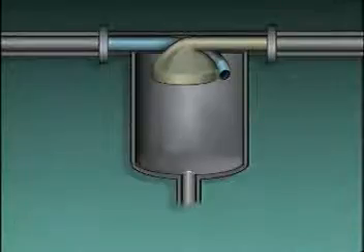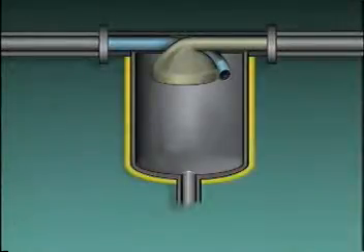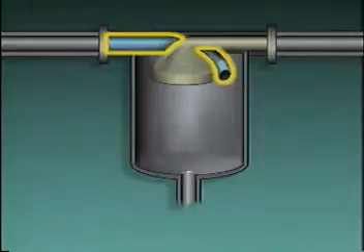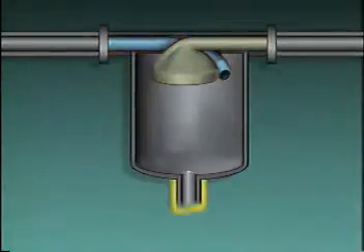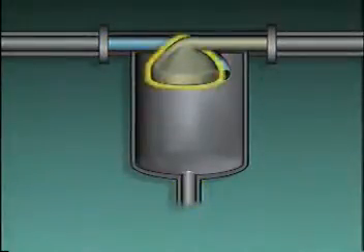To prevent this from happening, moisture separators or de-misters are often used to remove the droplets. This illustration of a de-mister includes a shell, a gas inlet line, a liquid outlet line, and a gas collector which is connected to a gas outlet line.